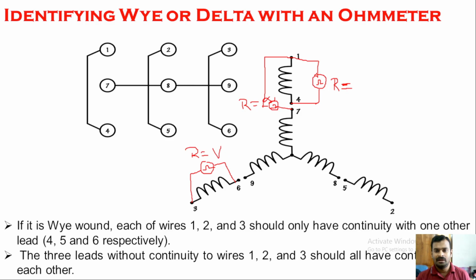So I got some value for 1 and 4, so this is one coil, and for 3 and 6 I got some value, which is another coil. Similarly, I am going to check the remaining terminals. 2 and 5 is going to give me some resistance. Now I need not measure between 1 and 4 again, and 3 and 6 I can avoid. So I measure with respect to 2 and 5, where I got some value. And if I measure between 2 and 8, it will be infinite. 2 and 7 is going to be infinite. 2 and 9, and 2 and 6 also are going to be infinite.